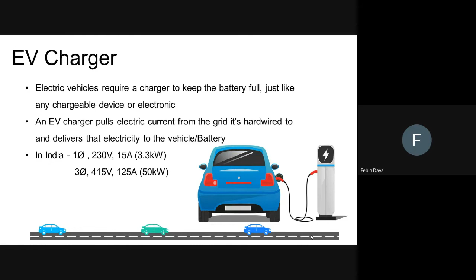This normally happens for a bigger battery charging station. The power lines come directly from the substation to the station, where I'll be installing a transformer. From the transformer, I can tap power at my requirement. So up to 50 kilowatt, I can conveniently use 415 volts three-phase AC supply.